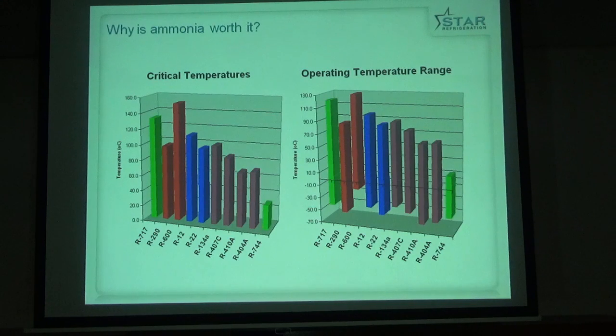in a heat pump. The other thing I'd ask you to note about this, if you compare ammonia with the blue columns, which were what I would call the old refrigerants, R12, R22, the purple columns are the replacements for them, the HFCs, R134A, 404A, and that kind of thing. As we move from the blue to the purple, notice that the critical point is getting lower. The replacement chemicals as refrigerants have been a compromise, and one of the things that's been compromised as a trade-off against having a lower global warming potential or a lower ozone depleting potential is they also have a lower critical temperature, and therefore these new fluids are less suited to use in heat pumps than R12 and R22 were.